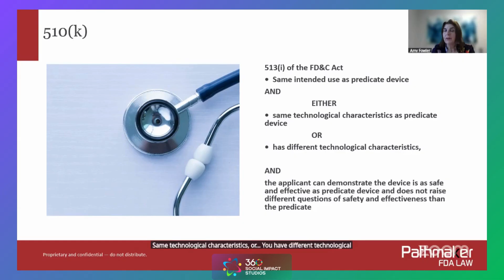So keep in mind that these submissions are supported by data, non-clinical performance data. So here are some examples. I brought up before, you might have human factors and usability required for a wearable. Can the person function the watch and the phone or the computer and make this work? If you have a software device, you might have to look into supplying software validation information. Things like, what are the requirements of the software? What is the architecture? How are you proving that this software actually works the way it is supposed to? So there's a lot of information there. You might have to have information about how the traceability for this particular software requirement applies all the way through the device life cycle and device use.